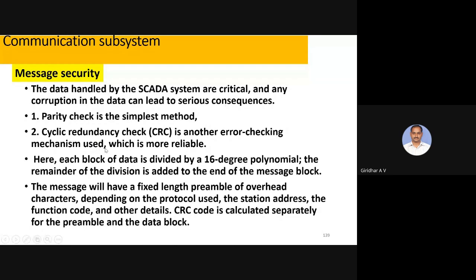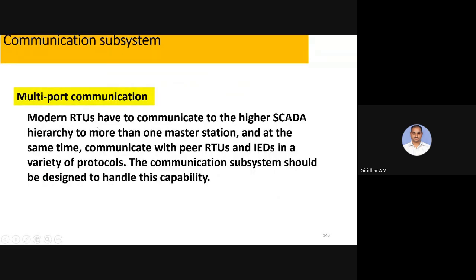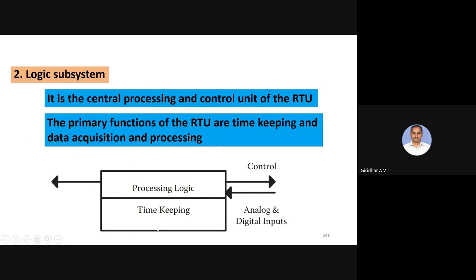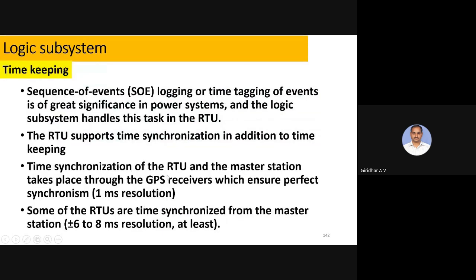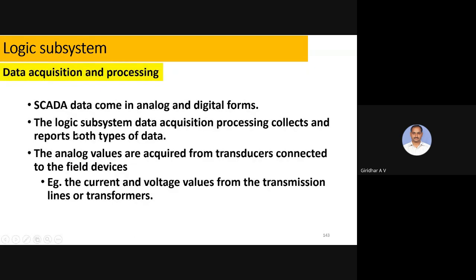So these cyclic redundancy checks will be done in an appropriate way, added to the main block of the data. So multi-port communications they are using. These are timekeeping and control actions; everything can be done with these logic subsystems of the RTU. So timekeeping, sequence of events, like different data sequencing, everything will be done. Even 8 milliseconds resolution can be done, very fast. Data acquisition processing also will be done.